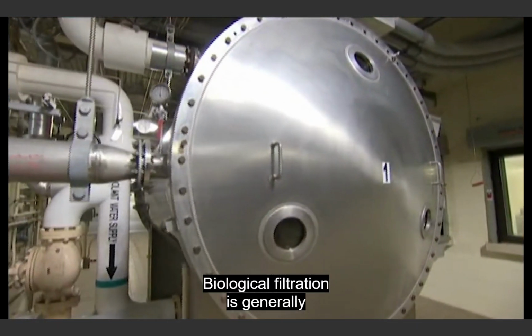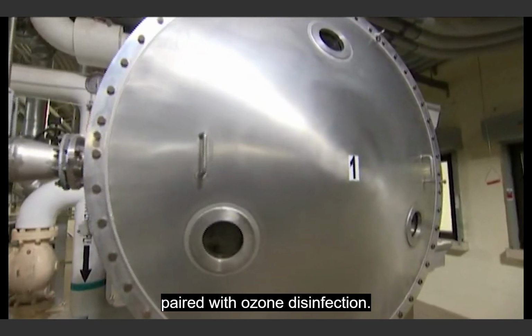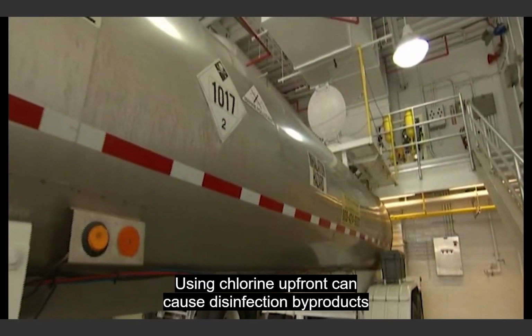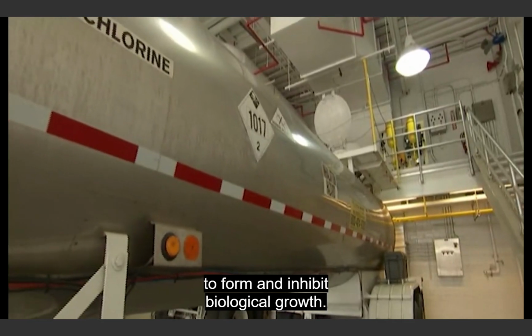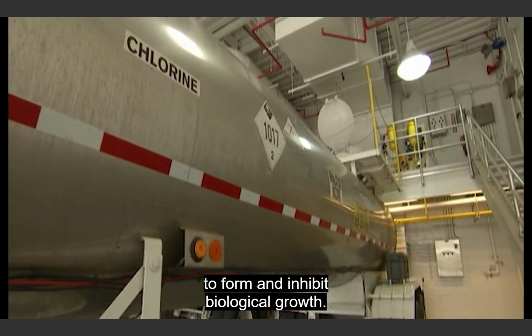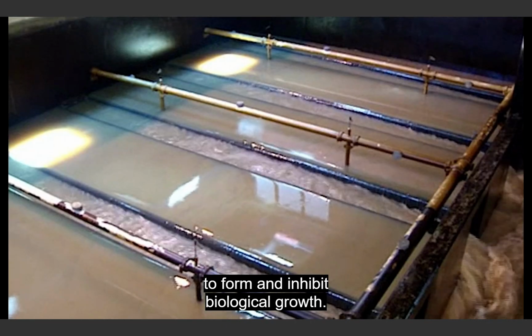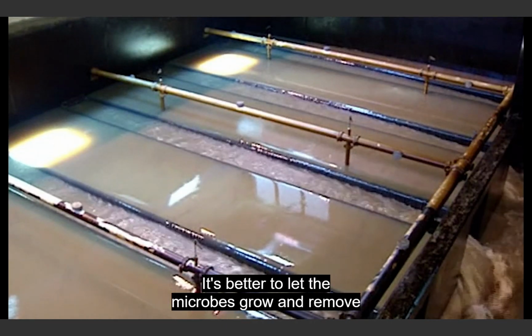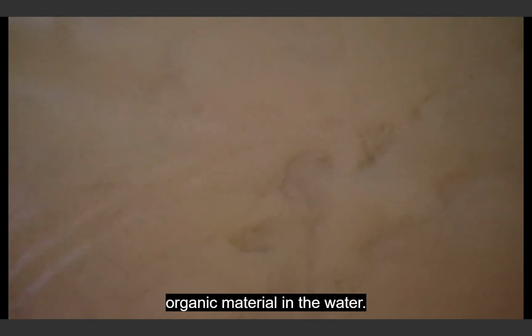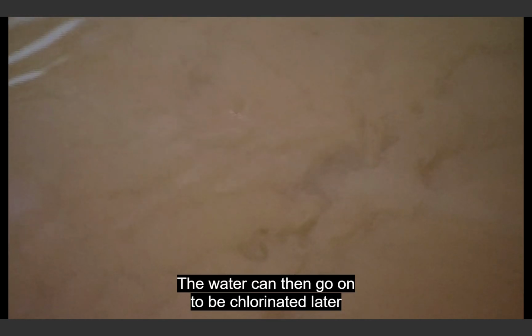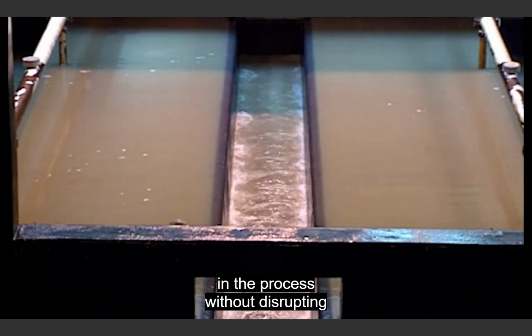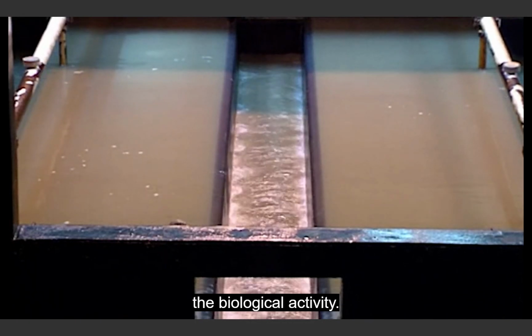Biological filtration is generally paired with ozone disinfection. Using chlorine up front can cause disinfection byproducts to form and inhibit biological growth. It's better to let the microbes grow and remove organic material in the water. The water can then go on to be chlorinated later in the process without disrupting the biological activity.